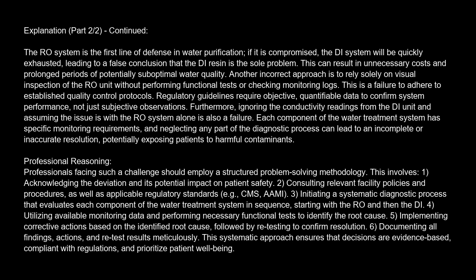Another incorrect approach is to rely solely on visual inspection of the RO unit without performing functional tests or checking monitoring logs. This is a failure to adhere to established quality control protocols. Regulatory guidelines require objective, quantifiable data to confirm system performance, not just subjective observations. Furthermore, ignoring the conductivity readings from the DI unit and assuming the issue is with the RO system alone is also a failure. Each component of the water treatment system has specific monitoring requirements, and neglecting any part of the diagnostic process can lead to an incomplete or inaccurate resolution, potentially exposing patients to harmful contaminants.